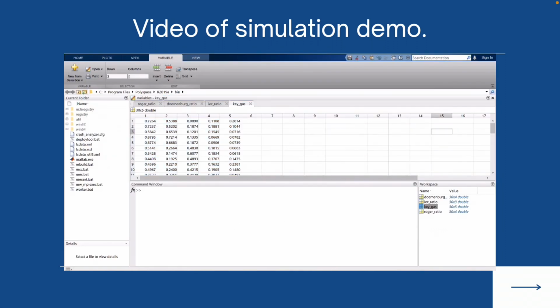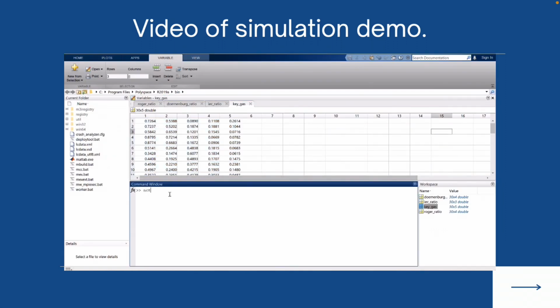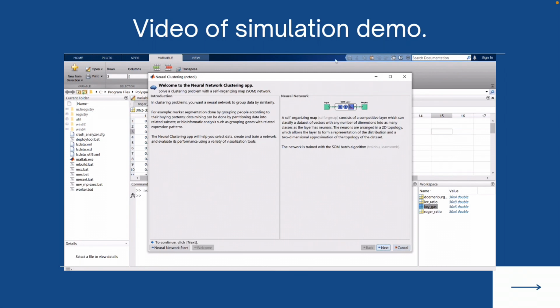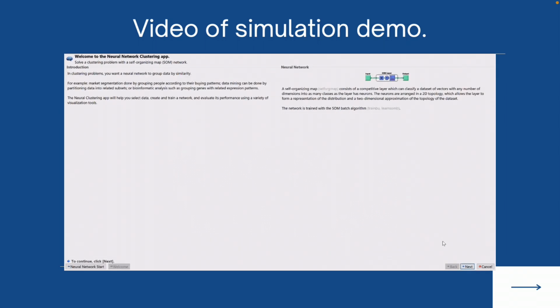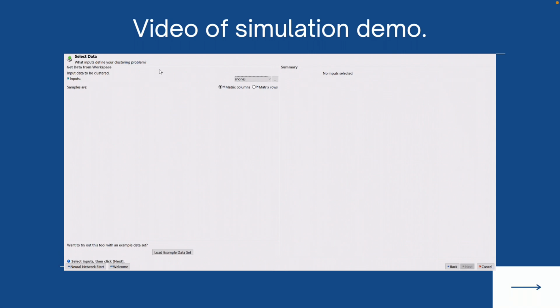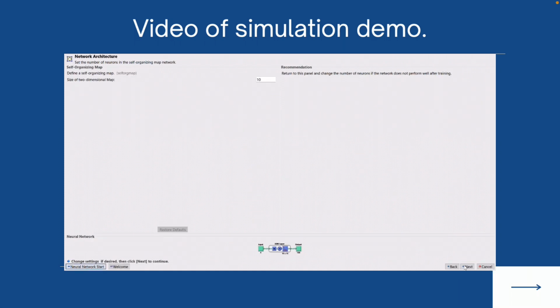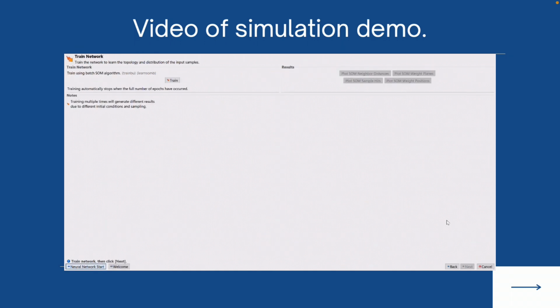After that, at the command window, type nctool to generate the neural network clustering app and continue next. At the input data, at the drop-down menu, select the method of input data that wants to be clustered and select matrix row so that it detects 3 or 4 gases ratio as input with 30 samples data. At define a self-organizing map size section, type 10, showing 10 size of 2 dimensional, so the output for the size of topology is 100 outputs, then next.